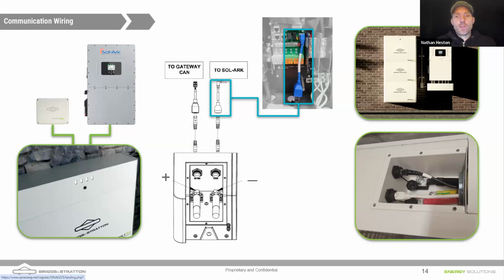Now, we offer an energy track platform. What you see on the left side of the screen is a Sol-Ark inverter above the battery, but you also see a gateway, and that gateway allows us to do individual battery monitoring. It allows us to monitor the bank on a module level and gives detailed information about each of the batteries: temperatures inside the batteries, high cell voltages, low cell voltages, a lot more information that we can pull through the Sol-Ark app. You also get to monitor the batteries through Sol-Ark, though. And Sol-Ark, I will mention later on how you can see some of that information in the Sol-Ark app.